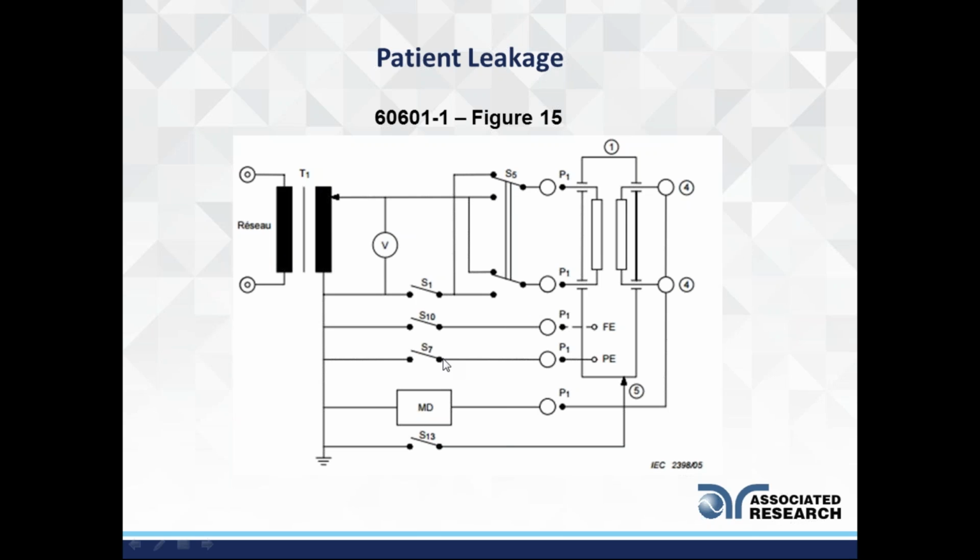I still have my protective earth switch, and I still have my MD with one side referenced to the low side of my input power, or T1, but the other side is now contacting a patient part on your medical device. So this might be, I don't know, a heart rate monitor or something that goes onto the body when you're in the hospital.